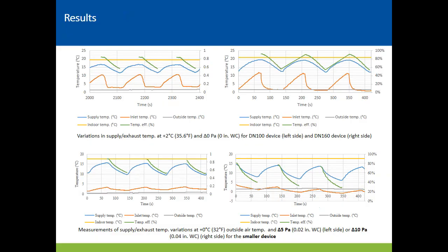As for the results, we actually tested 2 different sized units. One was smaller, with a size of 100 millimeters, and the second one was a little bit larger, 160 millimeters, to check whether this also influences their performance. And the results are like this. What you need to pay attention to is this green line, which represents the temperature efficiency, or the recovered heat efficiency.